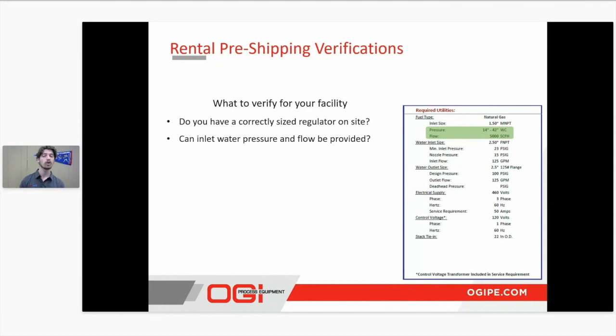Secondly, can the inlet water pressure and flow rate be provided at your site? For this one, we have your minimum inlet pressure sized as 23 psi. The minimum at the nozzle is going to be 15 psi. And as well, that inlet flow is going to be 125 gallons per minute. So you have that inflow coming in. You want to verify that your facility is able to give that 125 gallons per minute with the proper pressure for this unit to operate at its peak conditions.